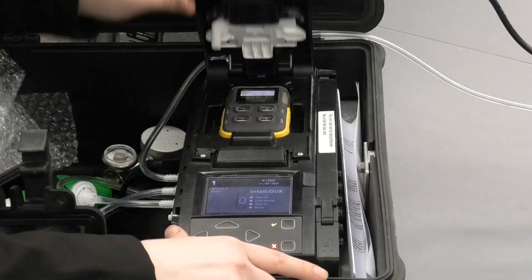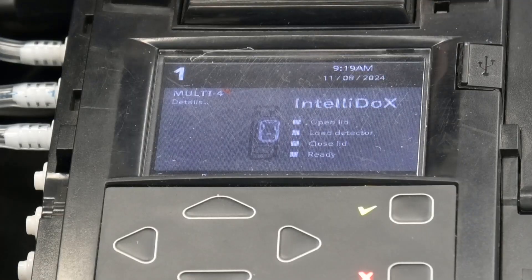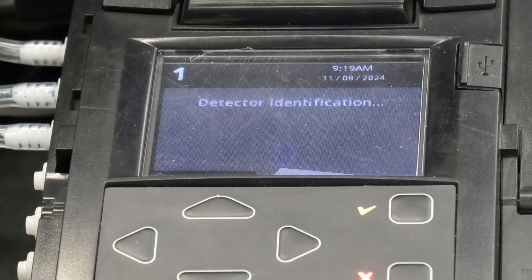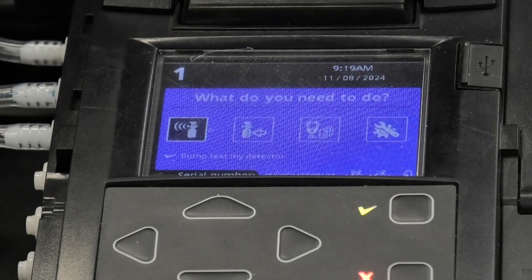So simply insert the gas detector — for this video I'm using the MULTI-4 — and close the lid. The Intellidox starts detecting the unit and, as you can see, the serial number also appears at the bottom. The configuration is complete and it's recognized.